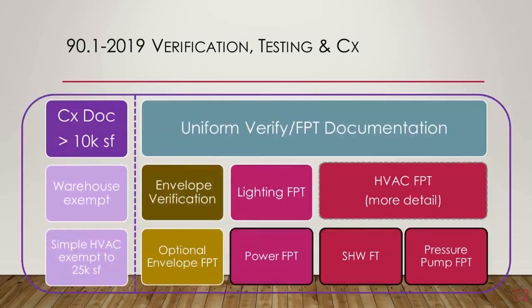So if we move into 2019, for verification, testing, and commissioning, we first of all put in place uniform documentation across mechanical, lighting, and service water heat, and power for functional performance documentation. So that would all have one format and come together in at least similar formats so that the building official could look at something that was somewhat consistent. We added power, service hot water, and pressure pump functional performance testing, and we put more detail into what was required for the HVAC functional performance testing.